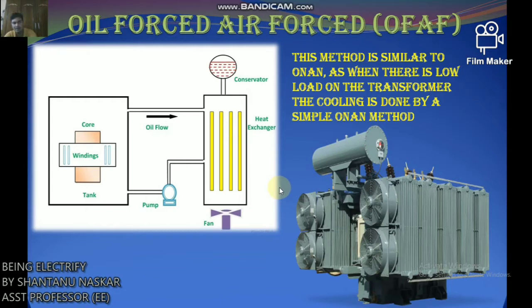This method is quite similar to ONAN, as when there is low load on the transformer, the cooling is done by the simple ONAN method. However, as soon as the load is increased, the generated heat will also be more, and therefore the sensor gives an alarm that the heat has exceeded the safe value, and as a result the fans and pumps are switched on automatically. Thus the cooling takes place by the OFAF method.